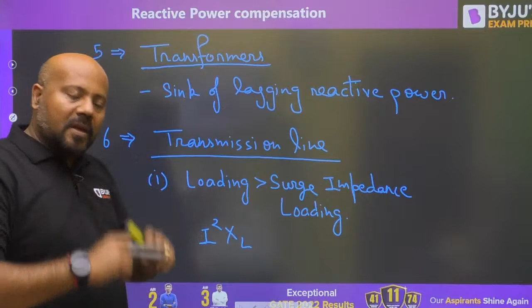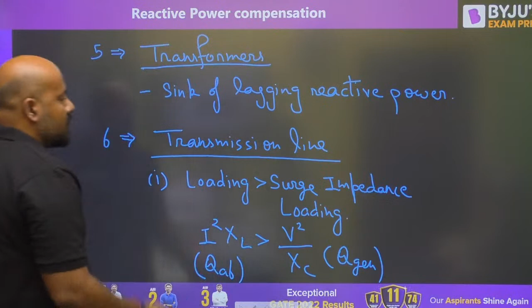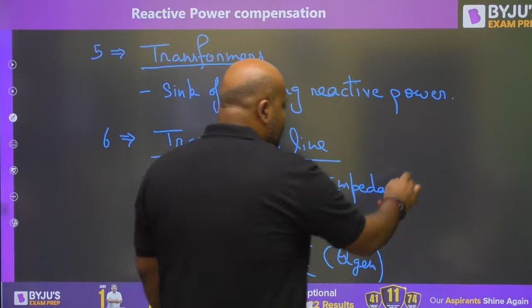When the loading is more than surge impedance loading, what is happening? You are saying, what is the reactive power absorbed? The reactive power absorbed is I square XL. What is the reactive power generated in the transmission line? That is V square upon XC. In this condition, the reactive power absorbed is more than the reactive power generated. What is going to happen? Your transmission line is going to behave as a sink of lagging reactive power.